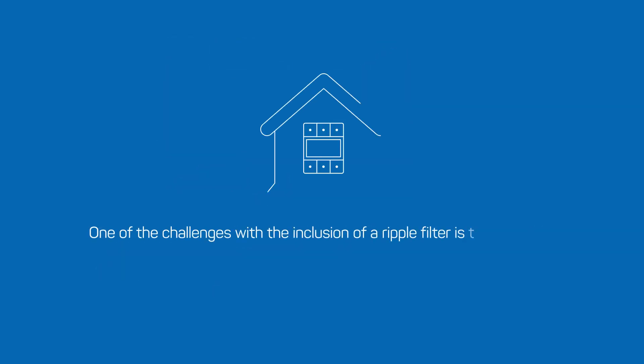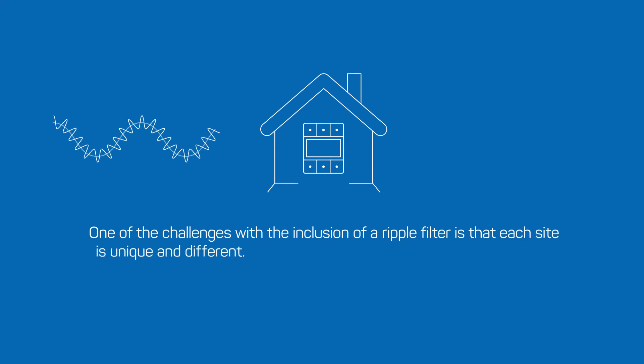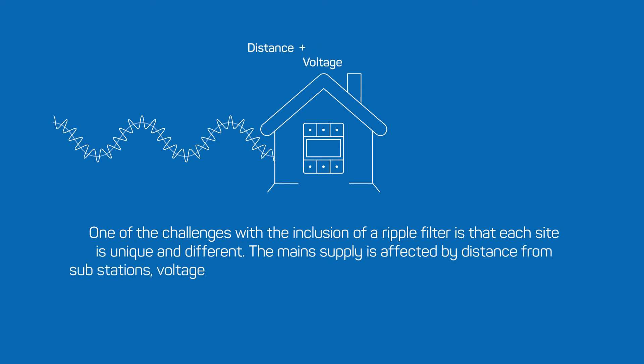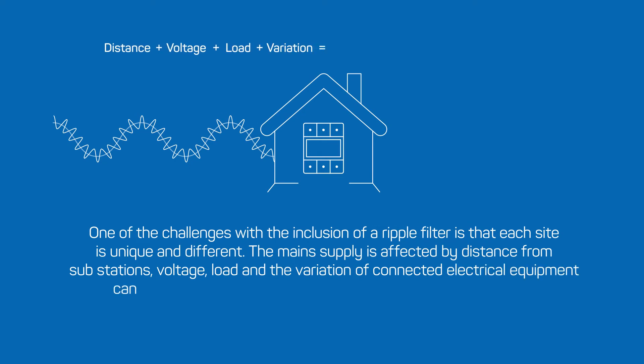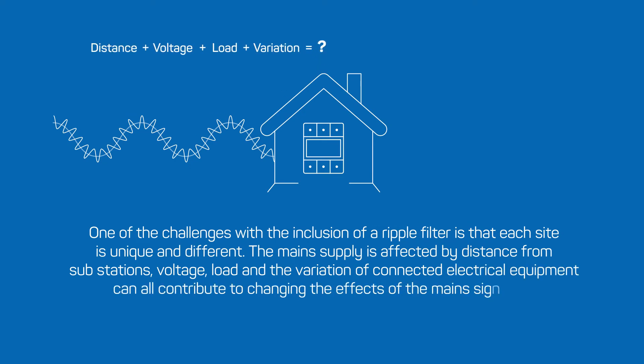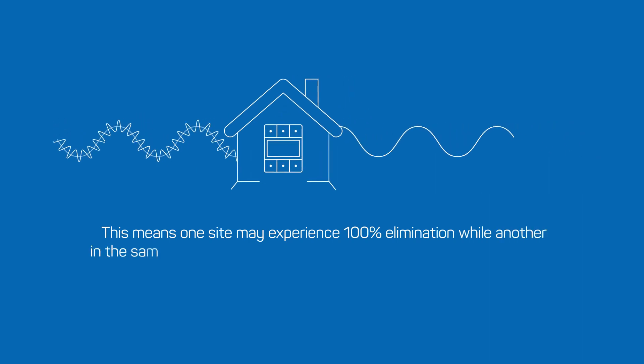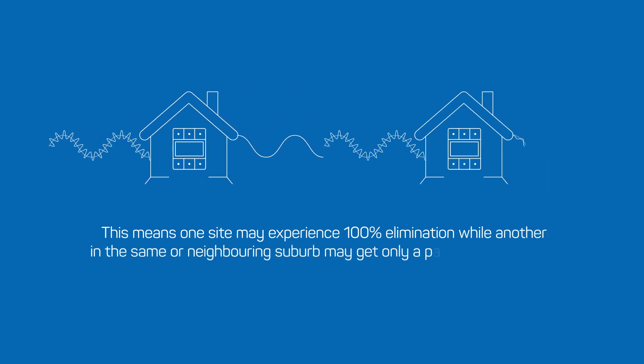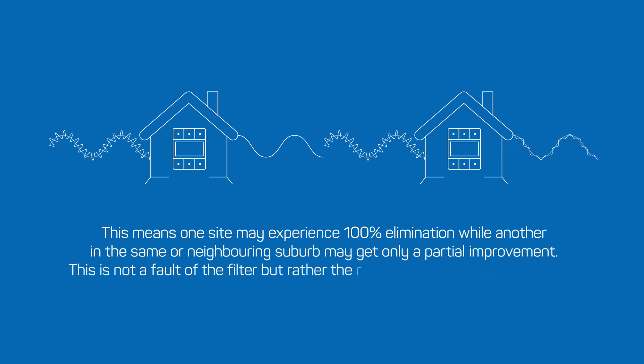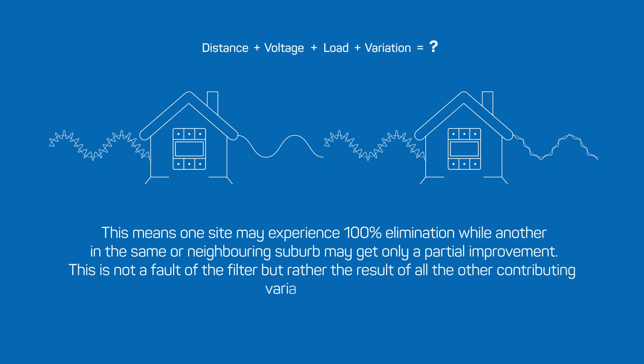One of the challenges with the inclusion of a ripple filter is that each site is unique and different. The mains supply is affected by distance from substations, voltage, load, and the variation of connected electrical equipment, all of which can contribute to the changing effects of the main signaling. This means one site may experience 100% elimination while another in the same or neighboring suburb may only get a partial improvement. This is not the fault of the filter but rather the result of all the other contributing variables involved.